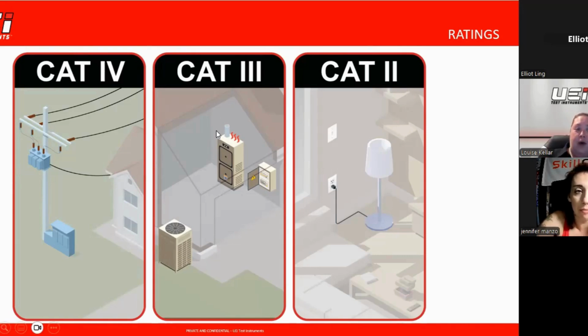So that's why your meter is rated in different categories. When you're looking at our meters, you'll see something like a Cat 4 rating up to 600 volts, and a Cat 3 rating up to 1,000 volts, that kind of thing. It's important to look at those because I've seen category 2 meters out there that people buy thinking they're appropriate, and that is not safe.